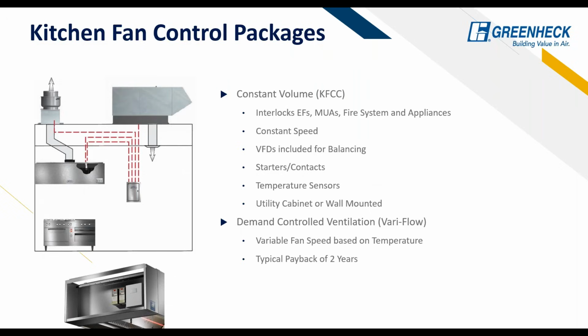Okay, and so now getting into some different control options we have. So we have the constant volume control. We'll have the interlocks with the exhaust fans, makeup air, fire system, and appliances, constant speed. Once this activates, you can either touch a button to turn it on, or like I said, there's a button on this thing you can activate to turn on the fans, or once the temperature sensor inside the hood starts to sense that the cooking appliances are on, it will automatically turn on. And with constant volume, it's automatically going to turn on to the top speed.